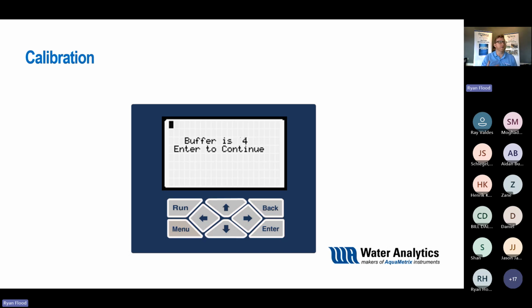Again, that is the beauty of this auto calibration: I put it into 4 and it knows that it is 4 based off of its readings. Now, if it's doing the auto calibration, a nice little trick here is if it says this could be 7 or this could be 10 and you have it in 4, it may indicate that you need to perform additional maintenance, which I'll walk through a little bit later.